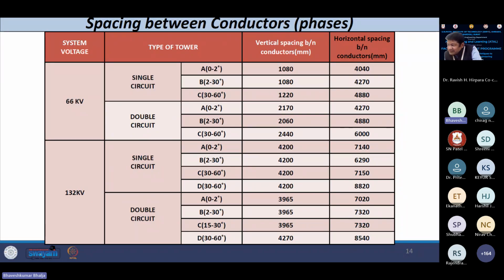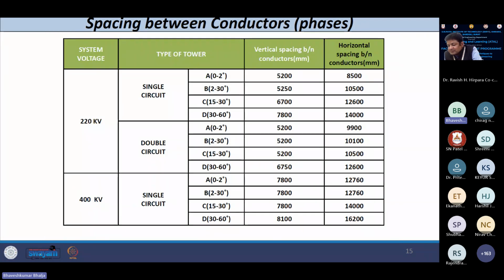I have mentioned the spacing, depending upon the vertical or horizontal configuration we use. This spacing is usually in mm, and as you go on increasing the voltage level, the spacing goes on increasing. If you look at 400 kV, the spacing is very high, almost close to 8 to 10 meters, or 12 to 16 meters if you use horizontal spacing. So chances of line to line faults are very rare.